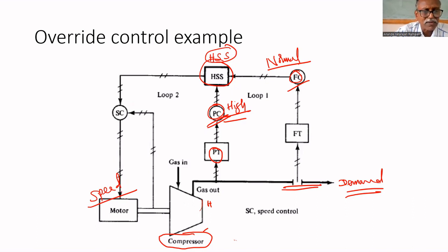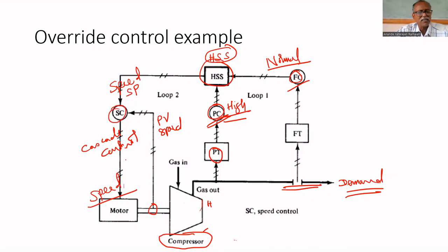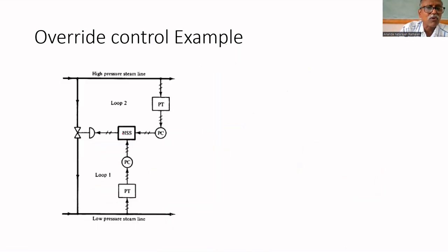Based on that selection, the speed of the motor will be adjusted. The set point to the speed controller is given by either the flow controller or the pressure controller — it is a cascade control. The speed is the process variable, compared with the set point, and based on that the speed controller will adjust the motor speed. That is another example for override control.